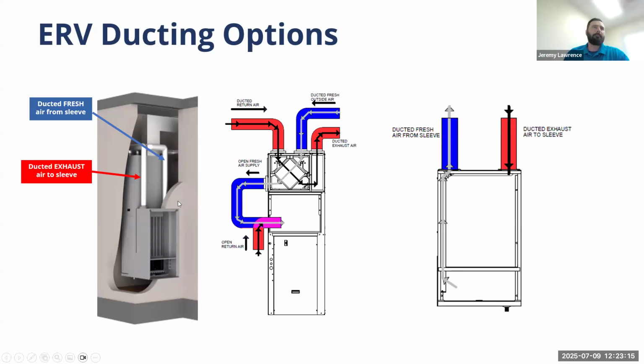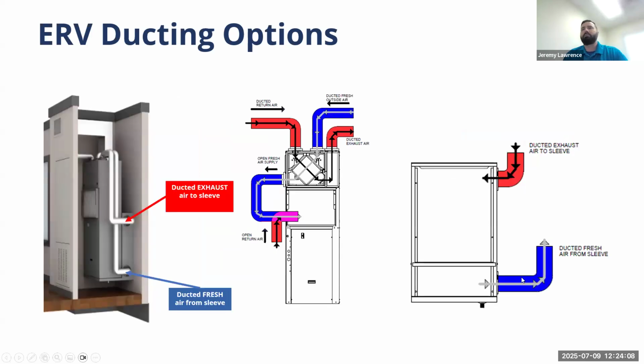Piping configurations, as you can see, top port installs are more common because of the space saving that they offer. There is a duct within the sleeve that, when the condenser fan motor is pulling in fresh air below, is pulling it up and then into the ERV. It can either be fully ducted and the stale air can be ducted from the bathrooms, kitchen, laundry room, etc., or it can be just released into the supply or pulled from the return space, which is the closet, up to your configuration and your application, how you'd like to see it. But just like any other ERV that you're used to seeing, any installation application will work. Side install, same deal, but with the connections on the side, a bigger closet space is required, which is why we don't see many of them, but the same options are available.